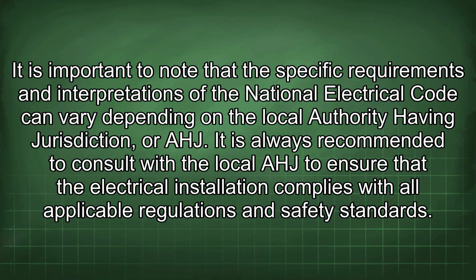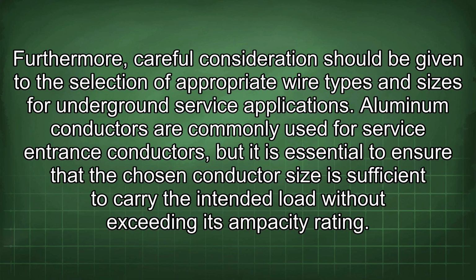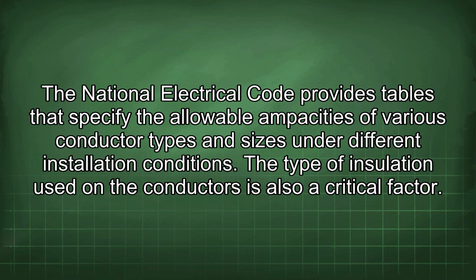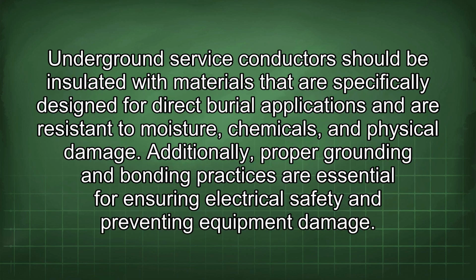It is always recommended to consult with the local AHJ to ensure that the electrical installation complies with all applicable regulations and safety standards. Furthermore, careful consideration should be given to the selection of appropriate wire types and sizes for underground service applications. Aluminum conductors are commonly used for service entrance conductors, but it is essential to ensure that the chosen conductor size is sufficient to carry the intended load without exceeding its ampacity rating. The National Electrical Code provides tables that specify the allowable ampacities of various conductor types and sizes under different installation conditions. The type of insulation used on the conductors is also a critical factor. Underground service conductors should be insulated with materials that are specifically designed for direct burial applications and are resistant to moisture, chemicals, and physical damage.